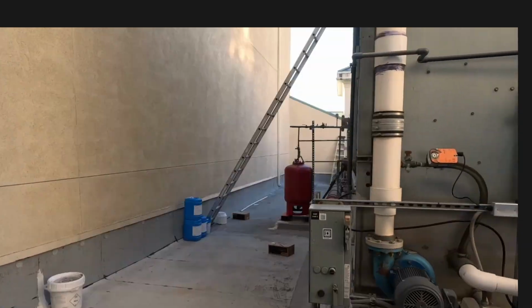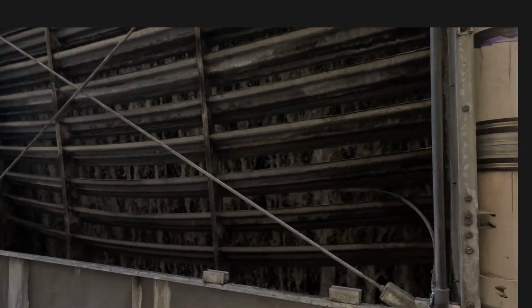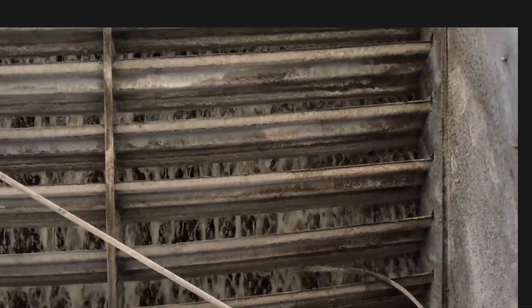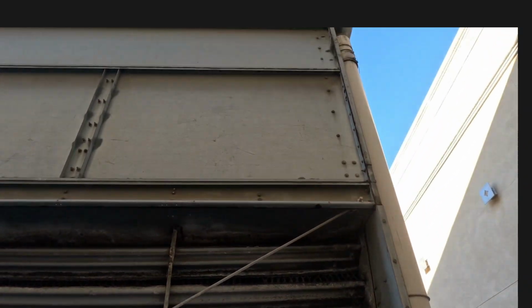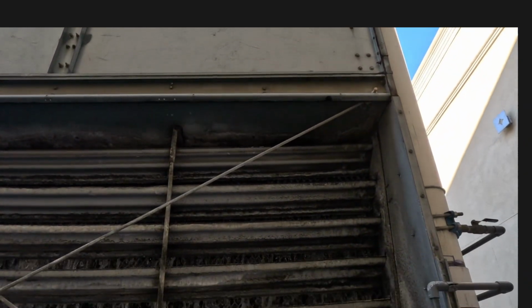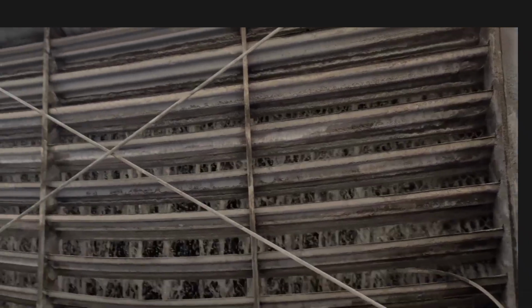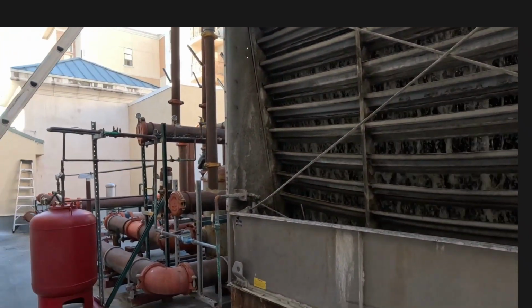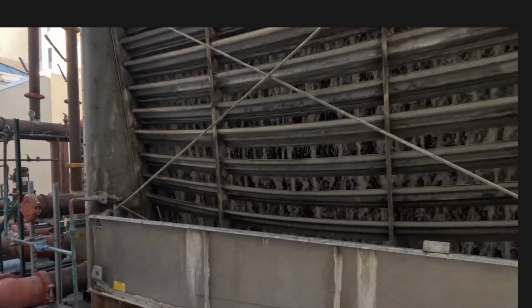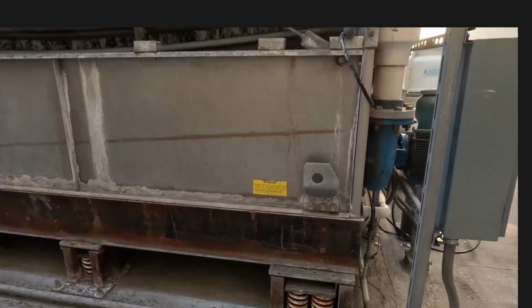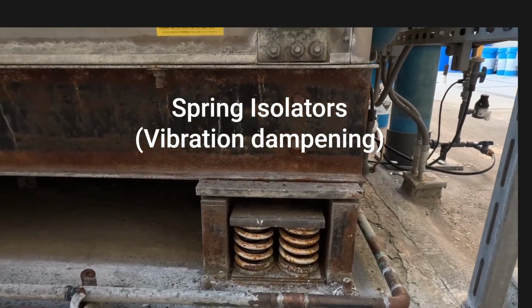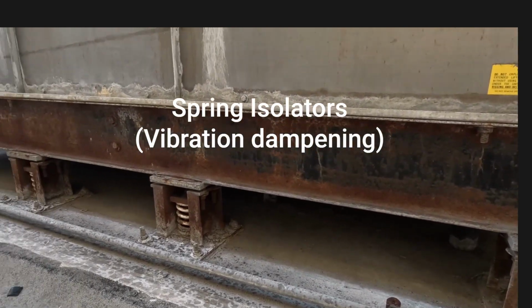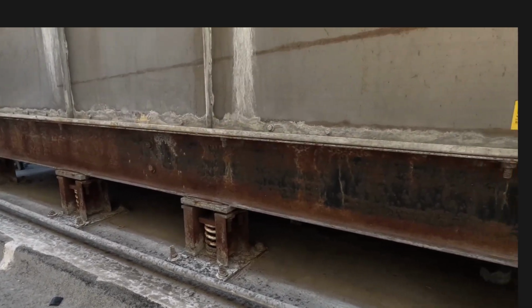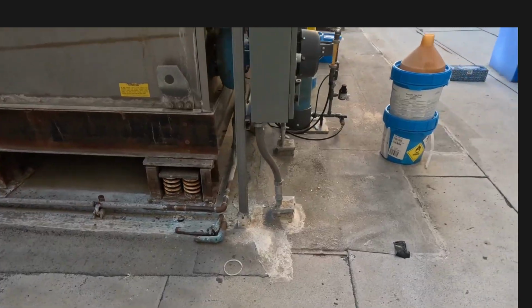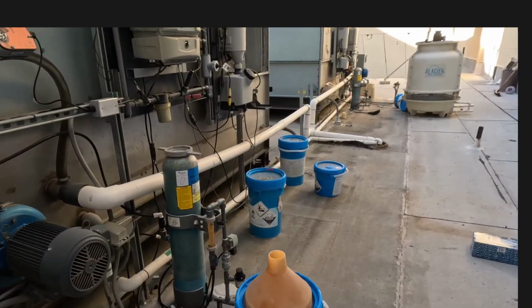As you can see, a temperature got triggered, and now the pump is starting to run with water raining down. That water is raining down from up top all the way down here. So you're using water to cool other water, or condenser water. Then here are your spring isolators. These provide shock absorption and vibration mitigation for your cooling tower, so the tenants down below don't feel all the vibration from this cooling tower.